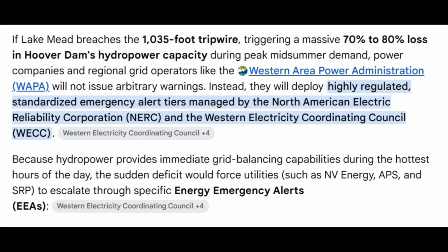That peak demand from Hoover, guys, is not in the heat of the day in that early afternoon. It's when they start losing solar power. They have massive solar fields, battery storages, and things like that they rely on heavily. But as the sun is setting, it's still hot, and the air conditioners are still running. So that's when they normally would kick in that instant hydropower. In other words, as soon as they release more water, the turbines increase, and that electricity is sent downstream.